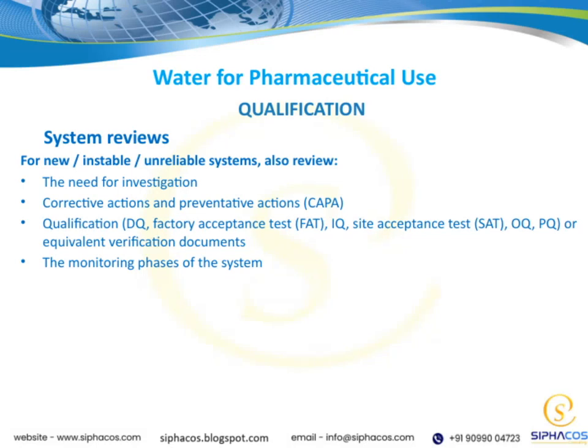When reviewing systems, especially new, unstable, or unreliable ones, it's important to take a comprehensive approach. First, we need to evaluate the need for investigation to identify any underlying issues. Then, we look into corrective actions and preventative actions, often referred to as CAPA, to address problems and prevent future occurrences. We also need to verify that the system has gone through proper qualification processes. This includes documents like design qualification, factory acceptance tests, installation qualification, site acceptance tests, operational qualification, and performance qualification, or their equivalent verification documents. These steps help ensure the system functions correctly and meets all requirements.